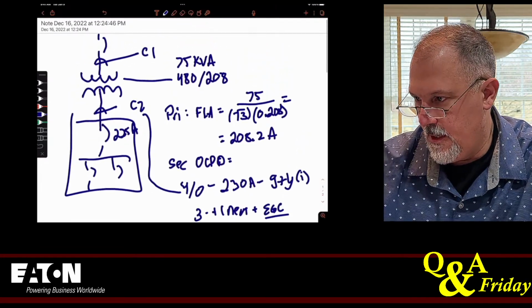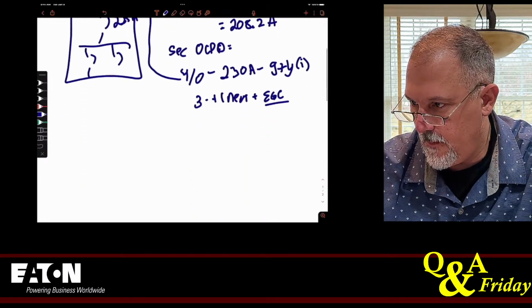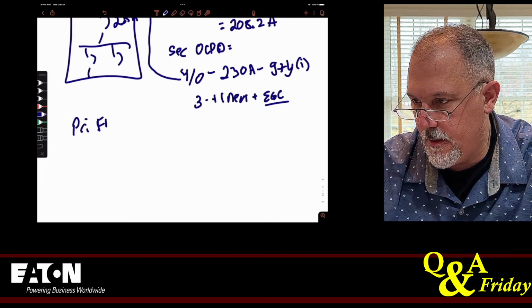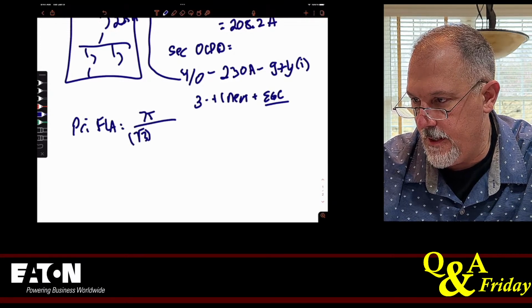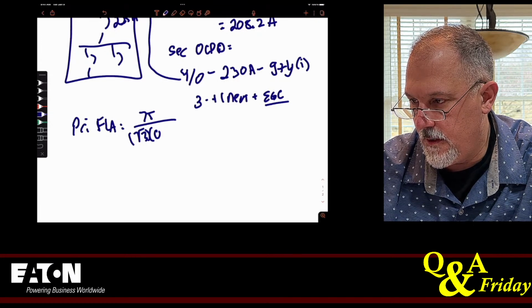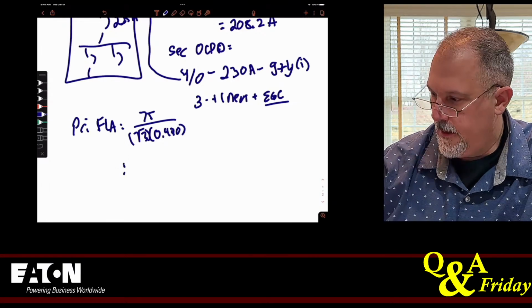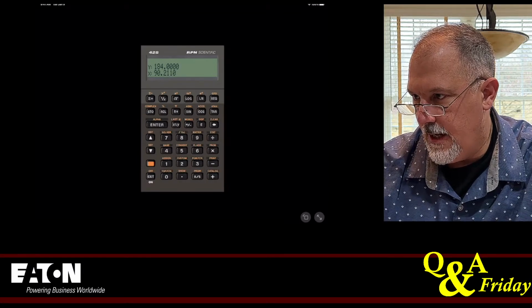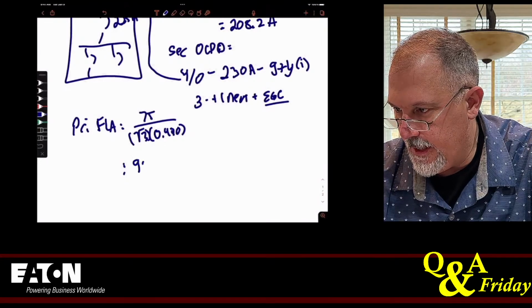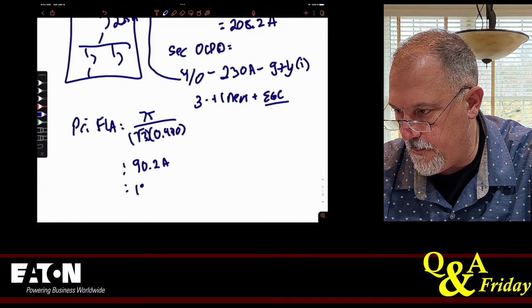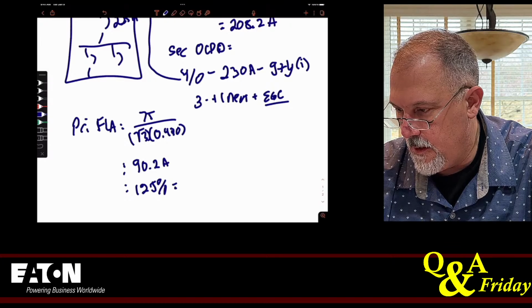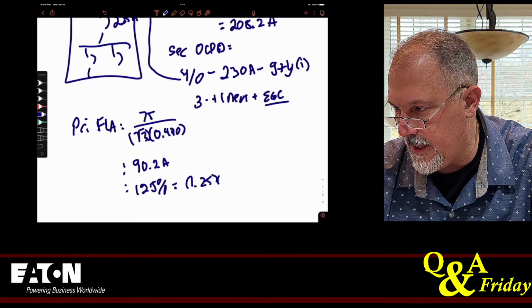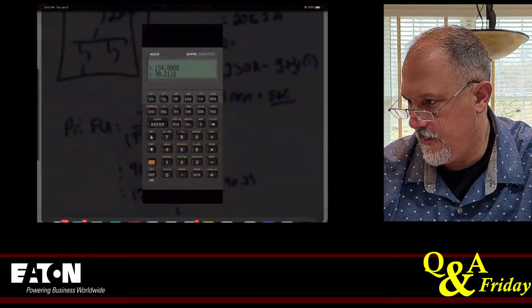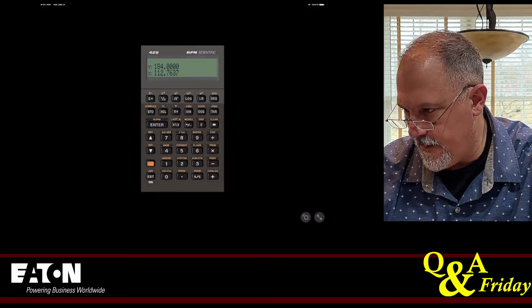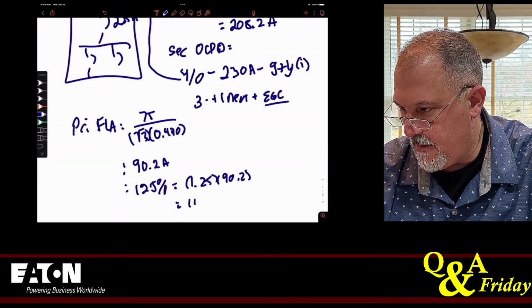Now let's talk about primary. So that's secondary, what about primary? Primary full load amps: 75 divided by square root of 3, divided by 0.480, is 90.2 amps. If I put it at 125%, I would take 1.25 times 90.2, and what is that? Say that's 112.